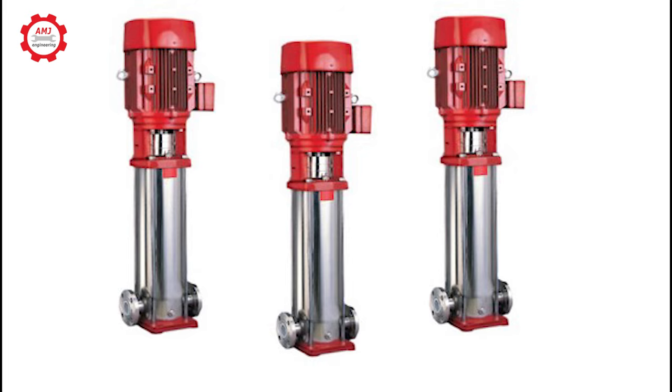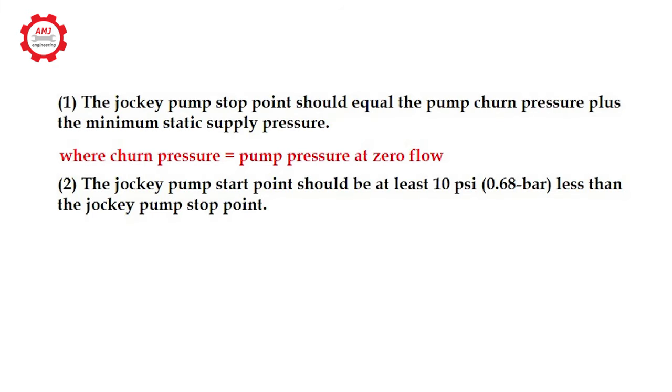Based on fire pump start and stop settings from NFPA 20, which states as follows: 1. The jockey pump stop point should equal the pump churn pressure plus the minimum static supply pressure. 2. The jockey pump start point should be at least 10 psi less than the jockey pump stop point.